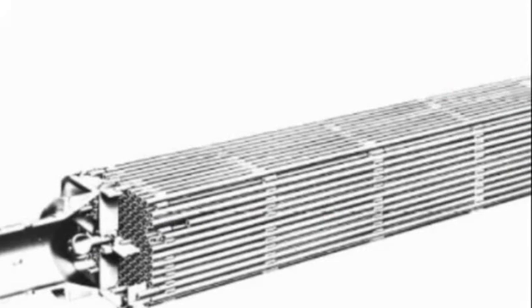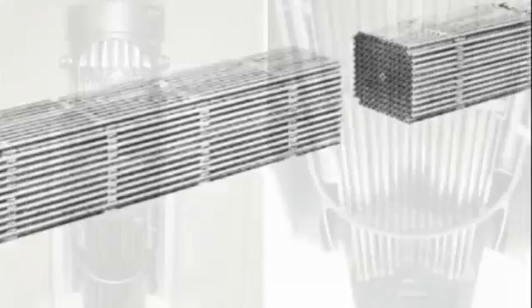Of course, the rack is distorted. So it wouldn't surprise me that in the course of emptying this fuel pool over the next year, they'll snap a fuel bundle. And you see the stack over there on the right? Well, that's connected now. So they'll pump the gases from inside that envelope up the stack and release them into the air. So it wouldn't surprise me that we'll get airborne krypton again, krypton 85, as a result of cracked and damaged fuel inside that fuel pool.